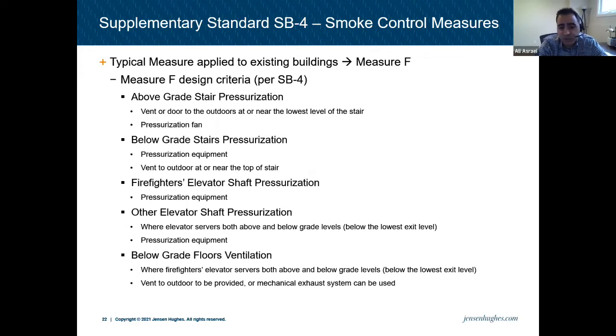The other thing is ventilation for below grade. So where the firefighter's elevator serves both above and below grade levels, again below the lowest exit level, we have to provide a vent to outdoors or mechanically exhaust the below grade floor areas. This is what I was talking about earlier, venting to aid firefighting. A mechanical system is not part of measure A to be considered as part of your smoke control system, but here specifically measure F is asking for that mechanical exhaust system for below grade floor ventilation. So if you have this scenario, with an elevator that serves both above grade and below grade, you need to have this vent to outdoors, which is typically not provided because the parking is, most of the time, entirely underground. So they use the mechanical exhaust system to vent that floor area. So that becomes part of your smoke control system here, right? And then the test and maintenance procedure is applicable to it.